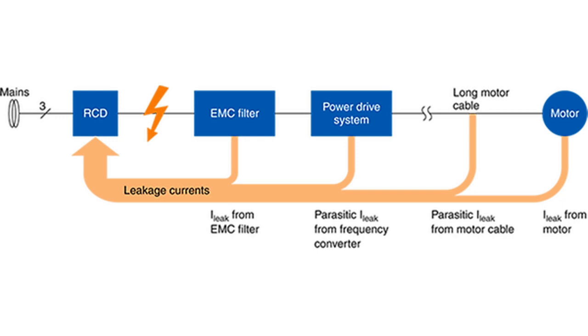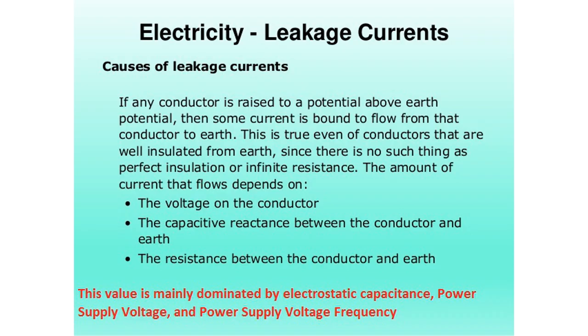Leakage Current: Leakage current is the current leaking from power supply lines to ground, when noise filters are inserted in power supply lines and a rated voltage is applied. This value is mainly dominated by electrostatic capacitance, power supply voltage, and power supply voltage frequency.